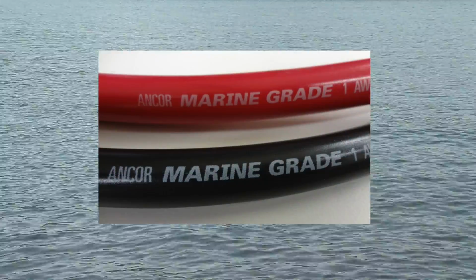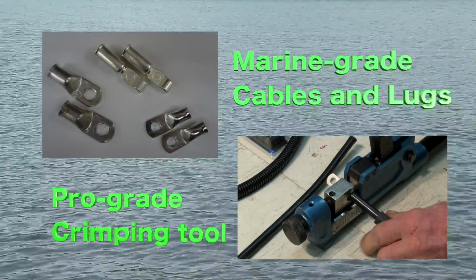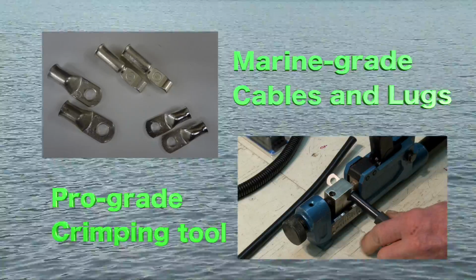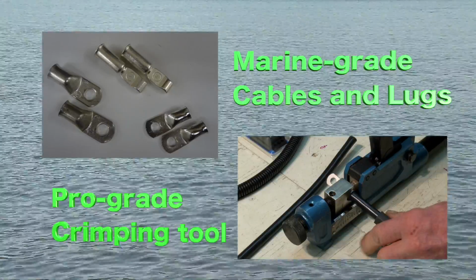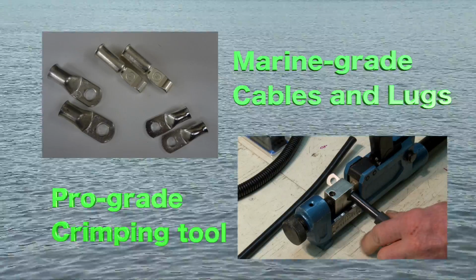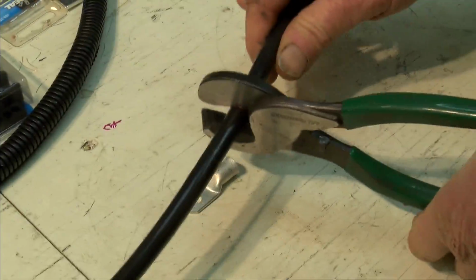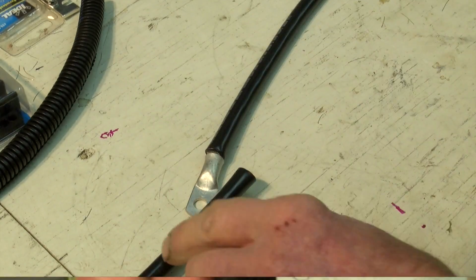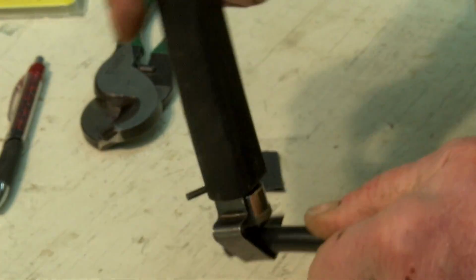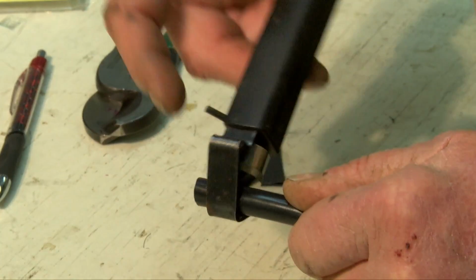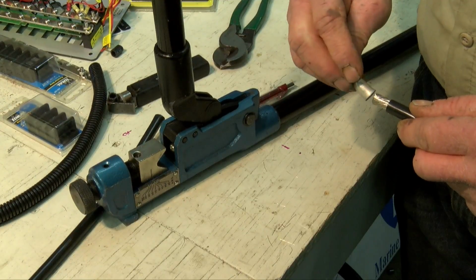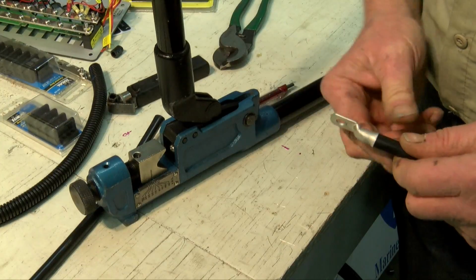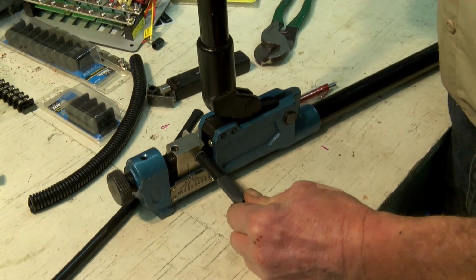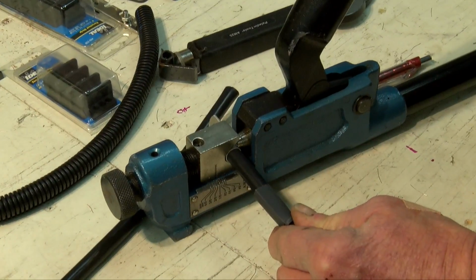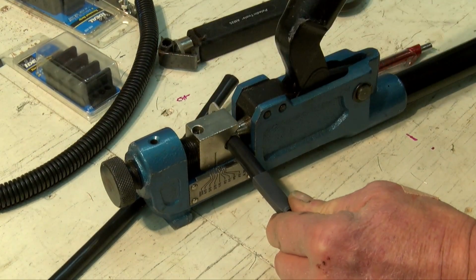Marine-grade battery cables are to be used exclusively. When making battery cables, be sure to also use marine-grade crimp lugs such as these, crimped with a professional-grade crimping tool. This is no place to cut corners or purchase bargain products. Remember that the battery cables have the same function as a fuel line to a combustion engine. Undersized, unprotected, or poorly laid out cables will limit performance and can be a safety hazard. Proper crimp connections are essential for efficient energy flow, which prevents energy loss to heat or possibly even fire.